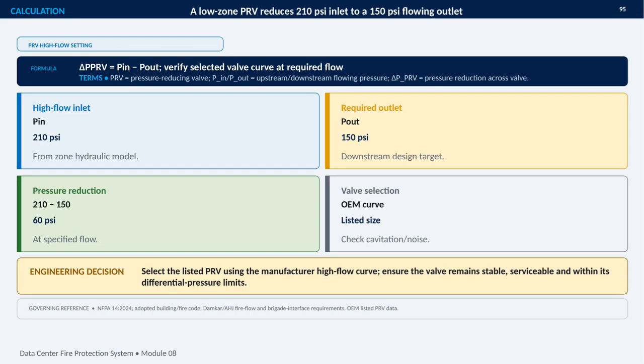The zone hydraulic model provides an inlet pressure of 210 psi, while the downstream design target is 150 psi under flowing conditions. The governing relationship is straightforward. Pressure reduction across the valve equals inlet pressure minus outlet pressure. So, 210 minus 150 gives a required reduction of 60 psi at the specified flow. That number is not, by itself, enough to select the valve.